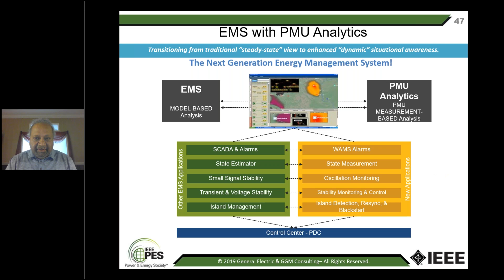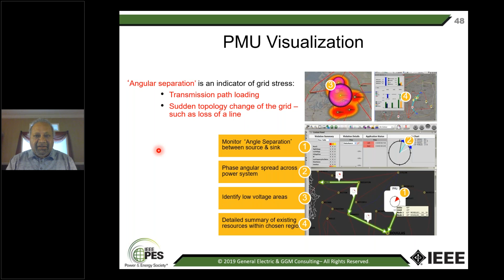So, PMU visualization: angular separation is an indicator of grid stress. If the PMU angle between any 2 points suddenly changes, either the transmission path loading has changed or the topology of the grid between the two has changed. So if the angle increases, that means the megawatts may have increased, or you may have lost the transmission line between those 2 points. The grid has weakened. So just measuring the angle difference between any 2 points is a very valuable indicator of problems in the grid.